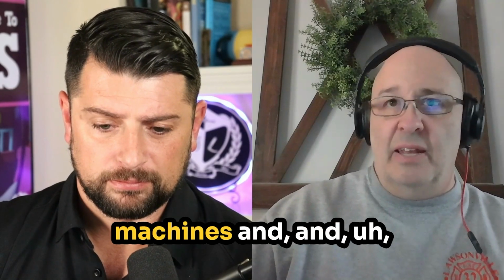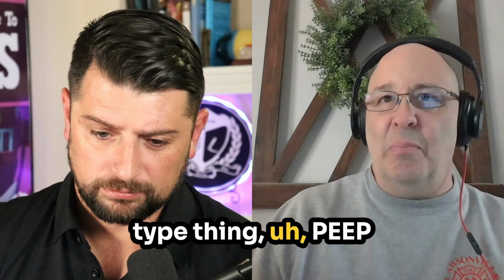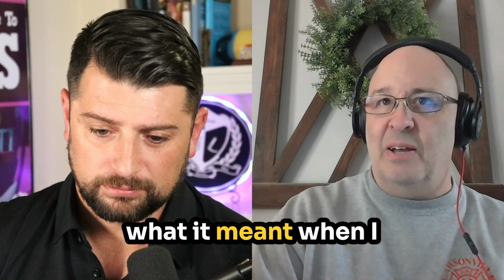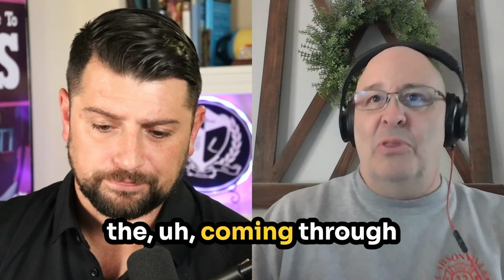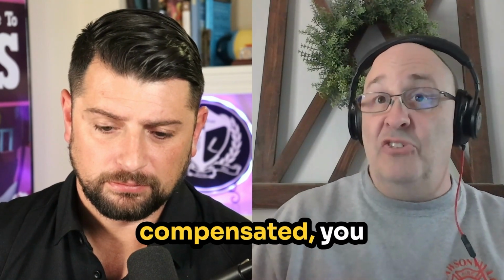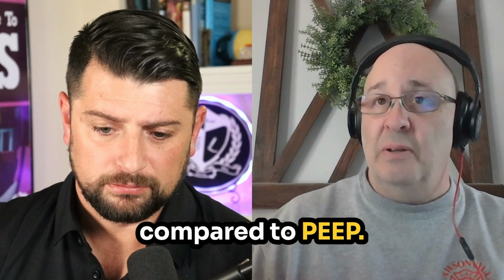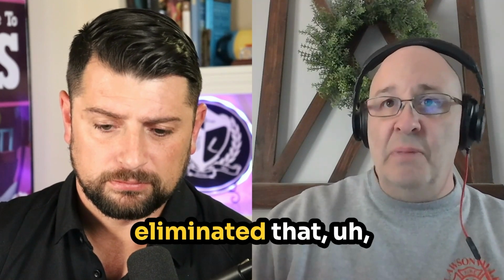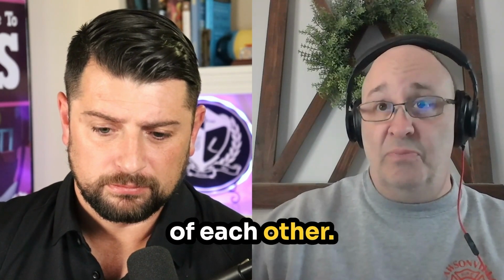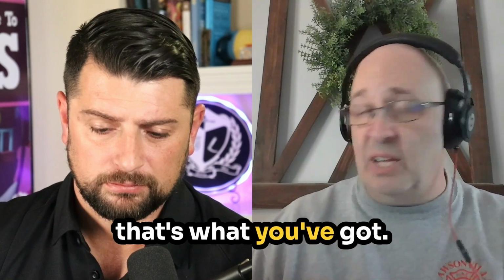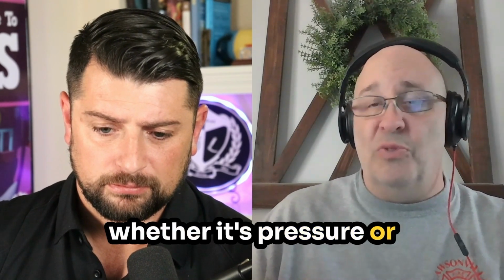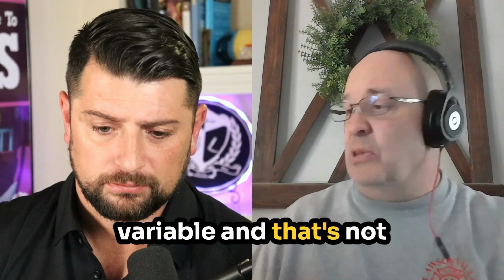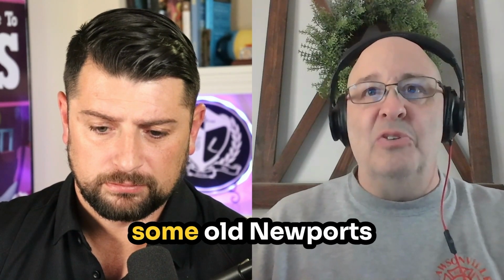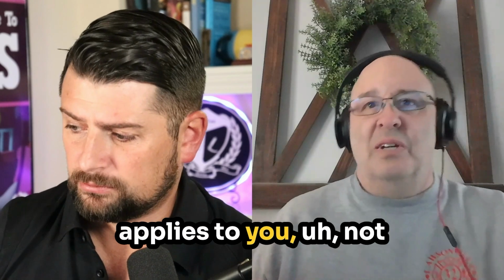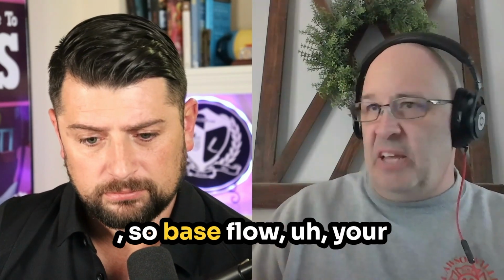Your more modern machines, and I admit this is an age thing, PEEP compensated. That's what it meant when I was coming through the RT world. You looked at sensitivity compared to PEEP. Your more modern machines now have eliminated that. They're independent of each other. So whatever PEEP you set, that's what you've got. Your sensitivity, whether it's pressure or flow, is an independent variable, and that's not related to that. But I still see some old Newports laying around that it still applies to. Not often, thank goodness.